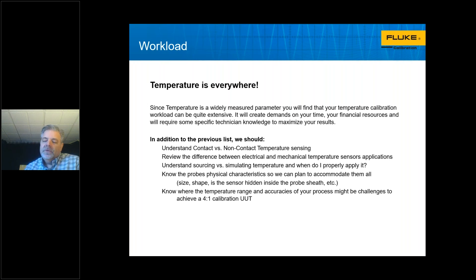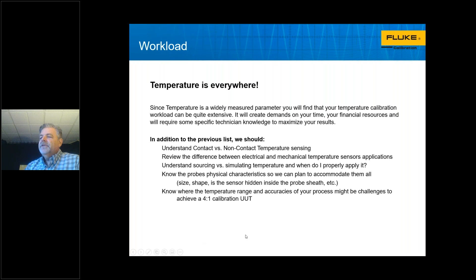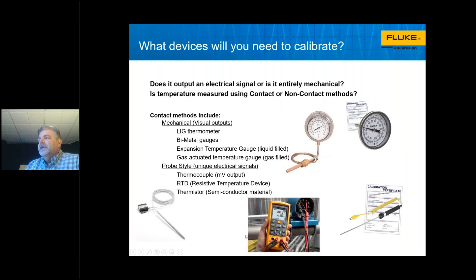We should understand the difference between contact and non-contact temperature sensing, and the differences between electrical and mechanical temperature sensing. The term UUT stands for unit under test. The industry standard minimum is to be four times more accurate than the unit you're testing. There are contact and non-contact methods for making temperature measurements.